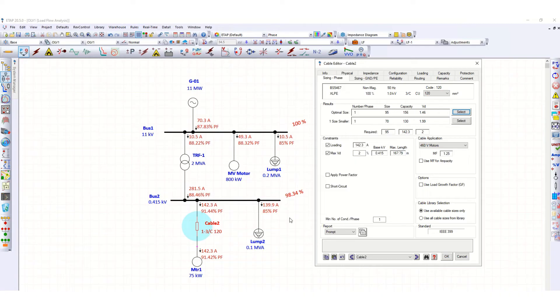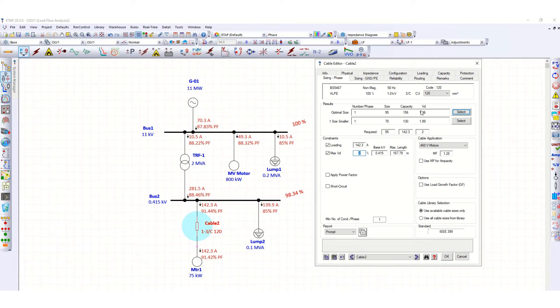Under the results, you can see the optimal size is single core 95 square mm, with a capacity of 156 ampere. The requirement is 142.3 ampere and the voltage drop is 1.46%, which is within the 2% maximum limit. So this cable size satisfies both the ampacity and voltage drop criteria.